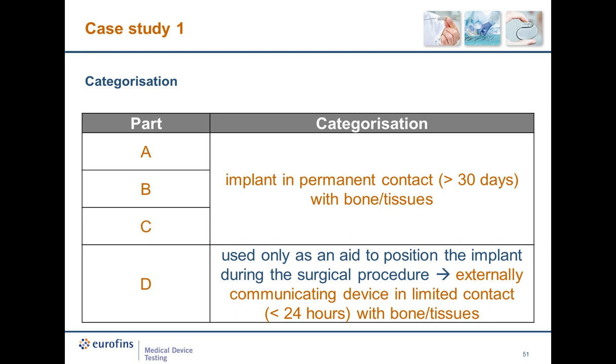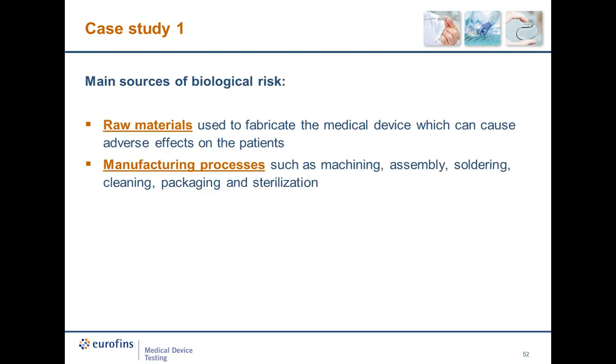The different parts have a different categorization according to ISO 10993-1. Parts A, B, and C are the actual implanted parts, therefore are classified as implant in permanent contact with bone tissue, while Part D is used only as a tool during the surgical procedure. Therefore, it's categorized as externally communicating device in limited contact, a few hours, with bone tissue. So the endpoints to be evaluated are different.